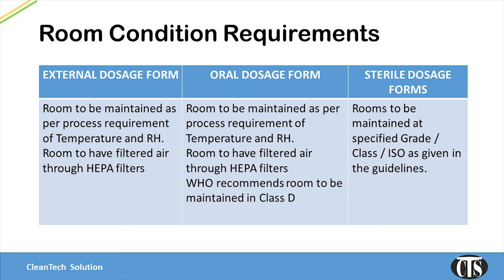Normally we have three types of dosage forms: external, oral, and sterile route. For these three different dosage forms, regulatory requirements of room classifications are different. For external dosage forms, air has to be supplied into the room through a HEPA filter to maintain cleanroom conditions. For oral solid or oral liquid dosage forms, air has to be supplied through a HEPA filter, and WHO recommends the processing zones should be in Class D area, although CDSCO has no such classification. In sterile dosage forms, since the product goes directly into the bloodstream, the manufacturing process is much stricter. Every single step of the manufacturing process is controlled by room classifications.